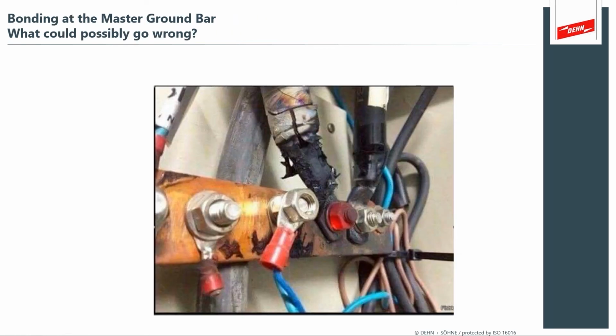And this is a really nice photograph that I've used in the past. And bonding at the master ground bar, what could possibly go wrong? Well, perhaps a loose nut or excessive neutral earth currents could introduce excessive heating and excessive currents on your bus bar. So a photograph like this shows you really bad practices. You've got perhaps loose connections, you've got a mixture of connections. So what's important here is to really pay attention to your neutral ground bar and to really pay attention to the connections at your master ground bar.